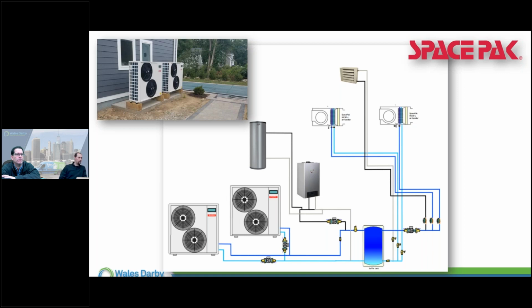So I saw somebody ask about the control strategy. This is automatic, we set a temperature. We could have had this thing come on based on outdoor temperatures where we handshake it from the heat pumps to the boiler, but we don't need to. We're all low temperature, and the heat pumps have been doing a phenomenal job just for heating and cooling. Every once in a while they hit some really cold temps.